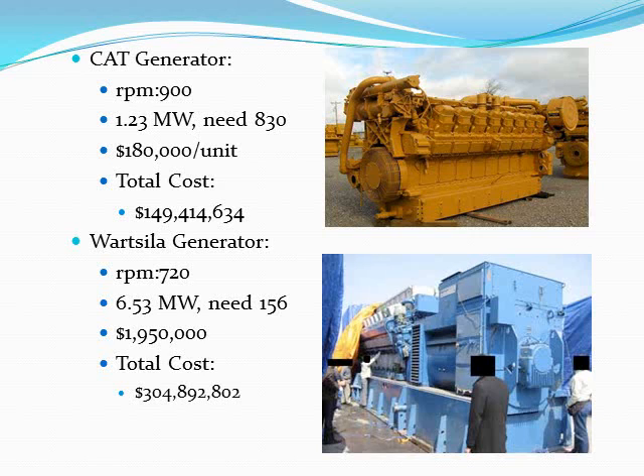which runs a little bit slower, about 720 RPMs. This puts out 6.53 megawatts of power, and to meet that Tracy power plant 1021 megawatt output, we would need about 156, maybe 160 of these, which would put us at a total cost of 300 million to start that power plant. This one puts out about 6 times more than the CAT generator because of its bore diameter and stroke, and it has 2 extra cylinders. The CAT generator is a 16-cylinder generator and the Wärtsilä has 18 cylinders.